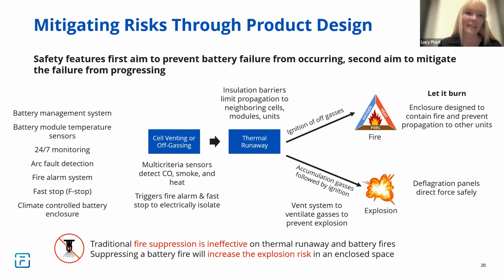One thing to note, we do not recommend using water on these systems. It's a highly energized system, although you can isolate that. If a first responder comes with their hose and puts a stream of water onto that battery, they become the grounding rod for that stored energy. So our message to the industry is, do not put water on these. Our recommendation is, if a system does go into thermal runaway, to let it burn, leave it there. We have controls and bunding in the system to make sure that any environmental impact from that is minimized. If we go to the next slide.